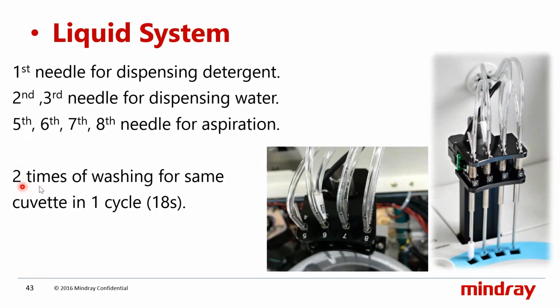And as I discussed, there are 2 washes for the same cuvette in one cycle. So this is called a cycle. I'll explain about a cycle. What does one cycle mean? One cycle means 18 seconds. In each cycle, we are also taking the reading. So every 18 seconds, the instrument will take the absorbance reading of the cuvette, and simultaneously the same 18 seconds, the cuvette wash will happen. In the same 18 seconds, a reagent will dispense and sample will dispense, and within the same 18 seconds, the mixer will mix. So simultaneously all the modules work within 18 seconds.